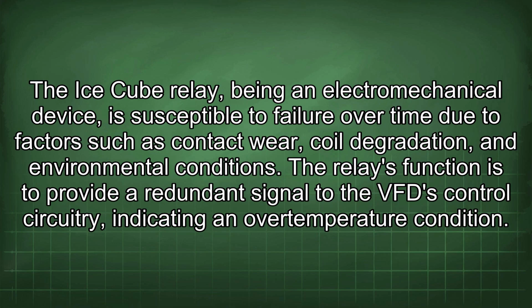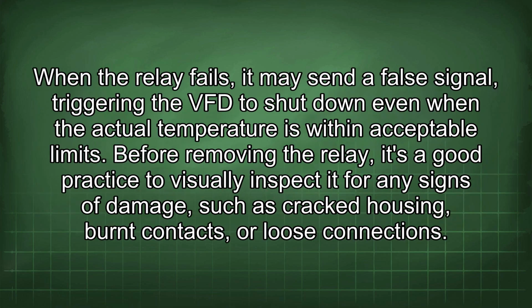The ice cube relay, being an electromechanical device, is susceptible to failure over time due to factors such as contact wear, coil degradation, and environmental conditions. The relay's function is to provide a redundant signal to the VFD control circuitry, indicating an overtemperature condition. When the relay fails, it may send a false signal, triggering the VFD to shut down even when the actual temperature is within acceptable limits.